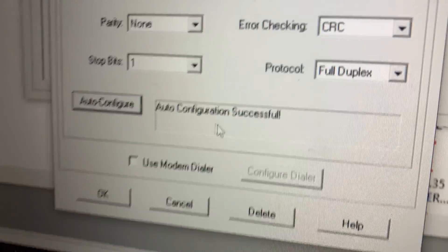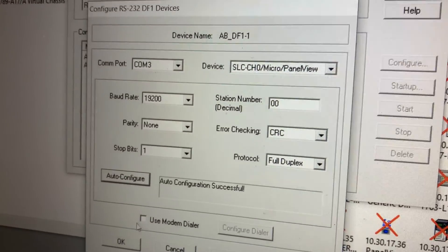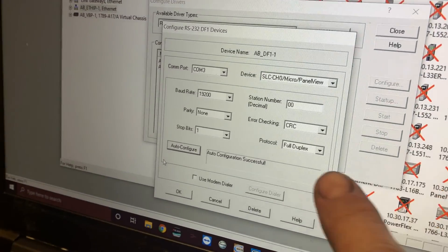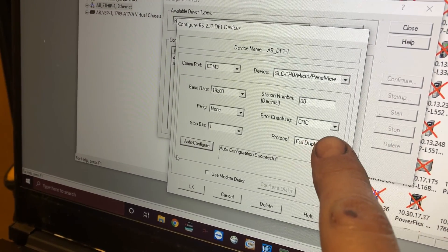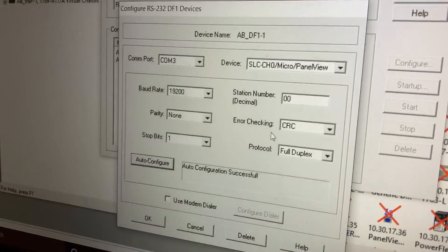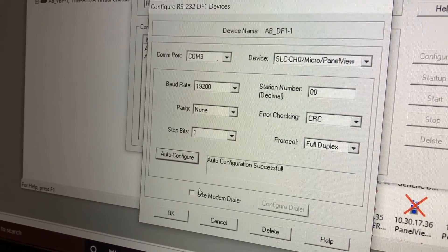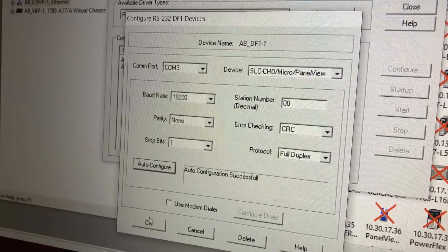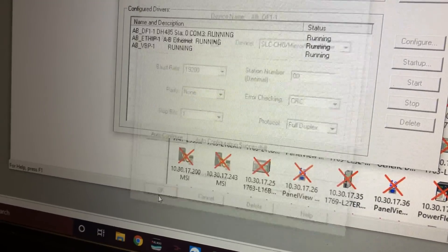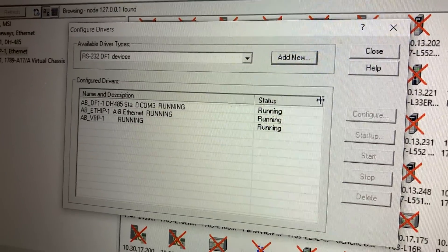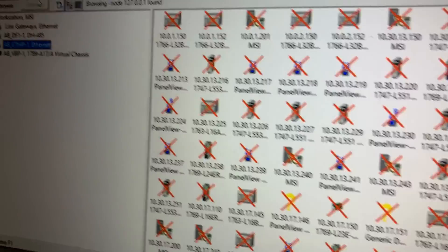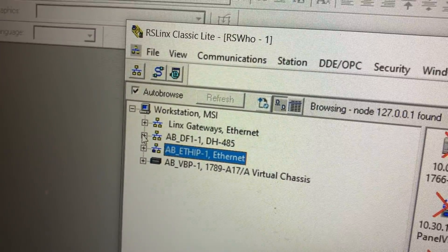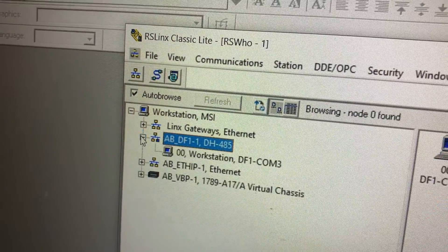Look at that. The one thing you've got to make sure of is that if you've got XON XOFF, your error checking is CRC. But as long as you've got it set up right on the PanelView, hitting Auto Configure will work. Go ahead and hit OK, and now you can hit Close. You'll see our new driver is the AB_DF1_DH485.